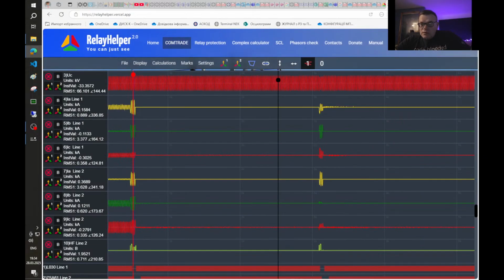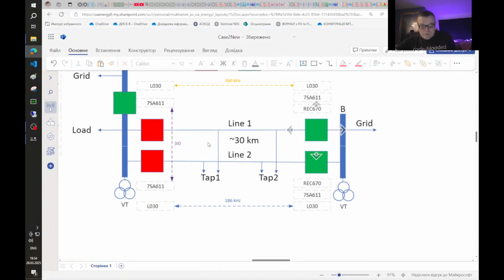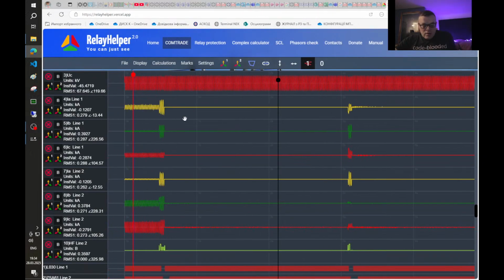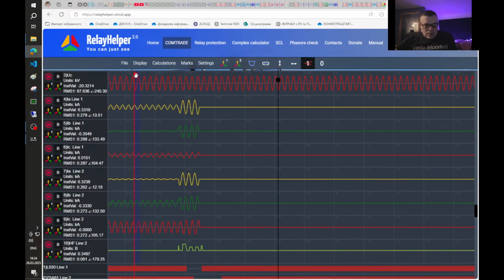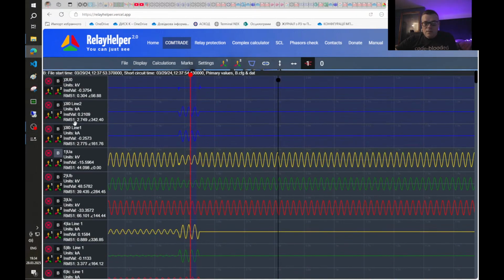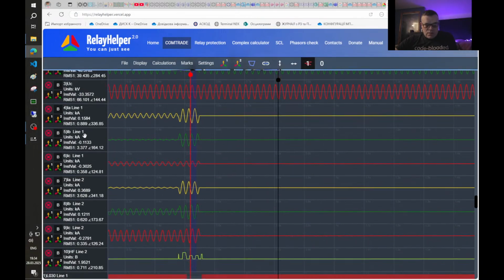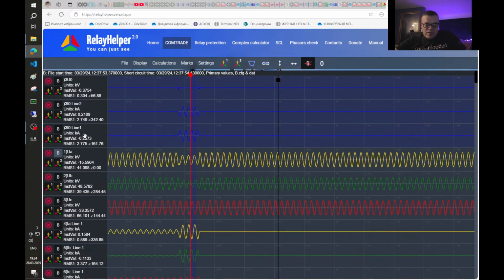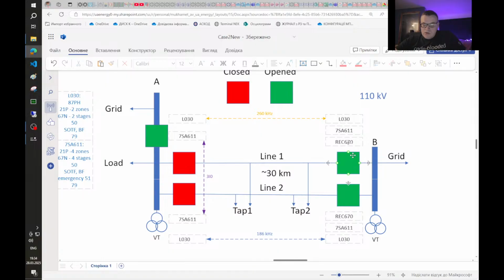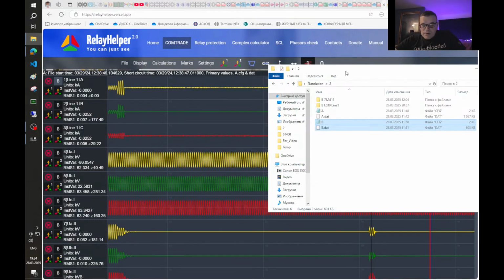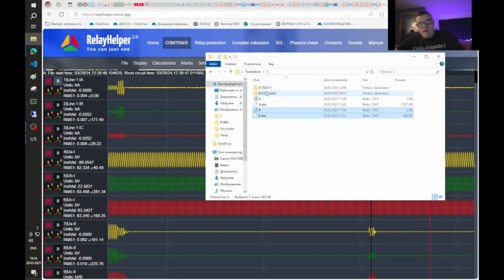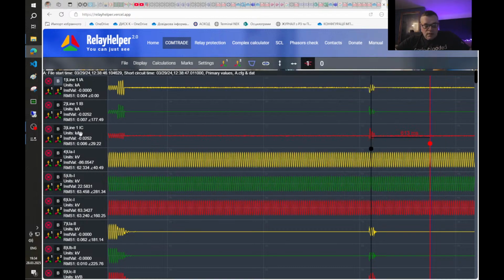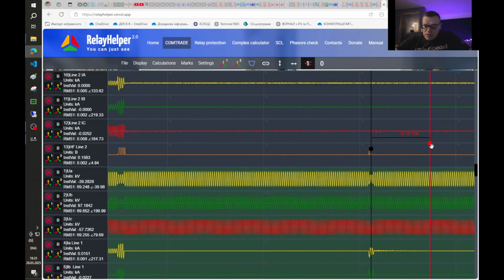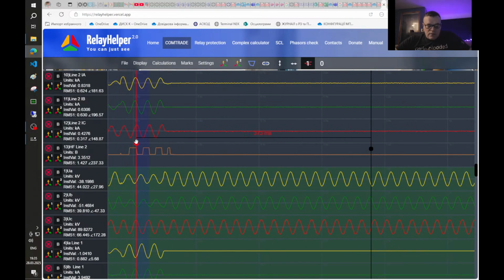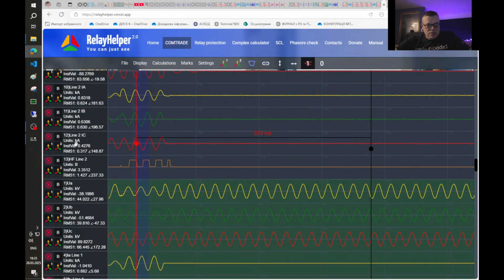So let's look at this. This is substation A. Let's analyze what tripped on the substation B side, because it's a little bit easier. From the substation B side we have records from the Siemens relay, and also from the LO30 from Hartron, and let's start from that. If we look at the high frequency communication signal, we can understand that this line was mostly tripped by differential protection.